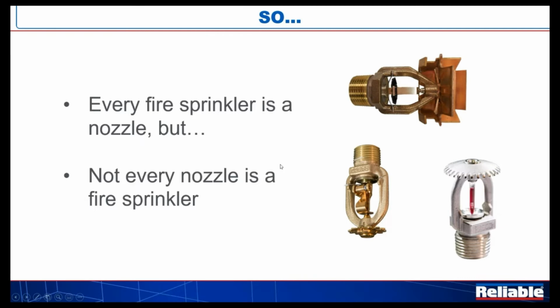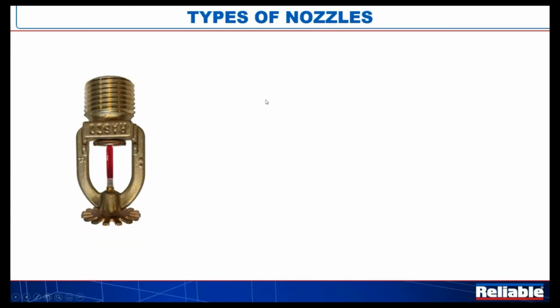Obviously, we don't have a thermal element. We don't need to worry about activation times. Typically not worried about deflector distances and things like that as it relates to activation. But again, they are different creatures, and they're defined not very clearly. And all the research led back to this thing that, hey, the differences between these nozzles is kind of nebulous, but we have these general characteristics that we work with. So what are the types of nozzles? Three types, basically: low velocity, medium velocity, and high velocity.